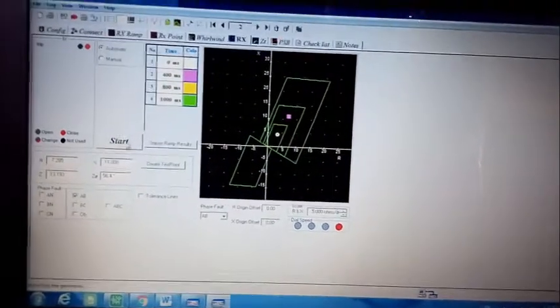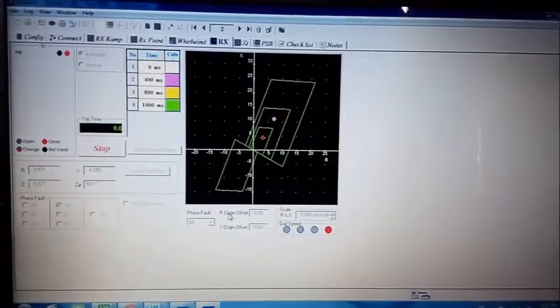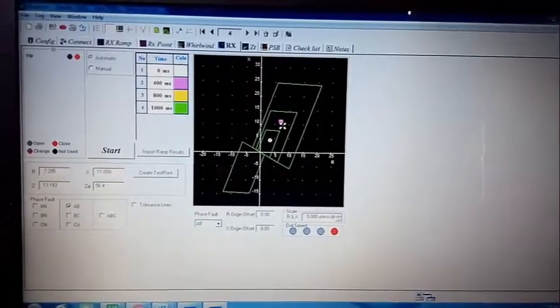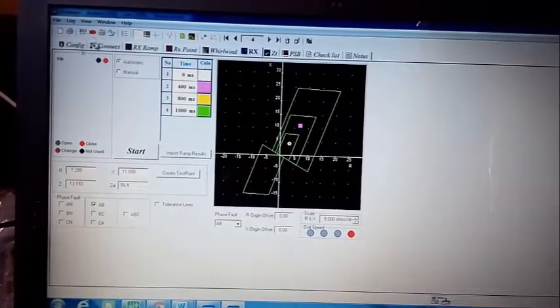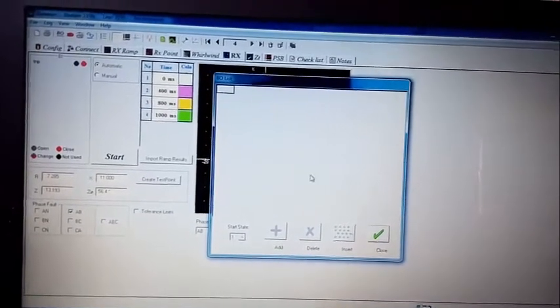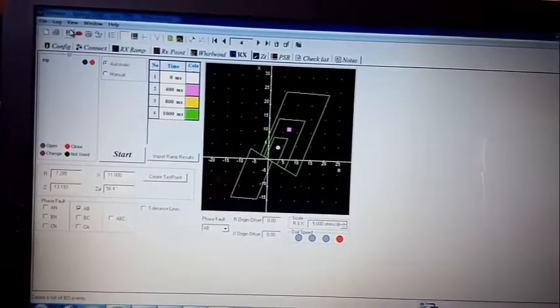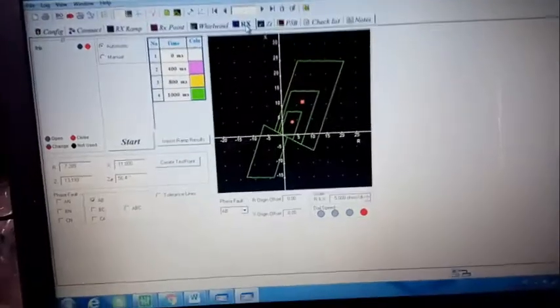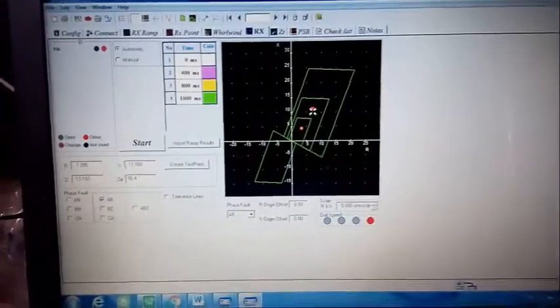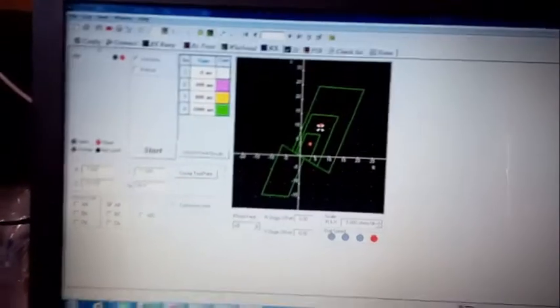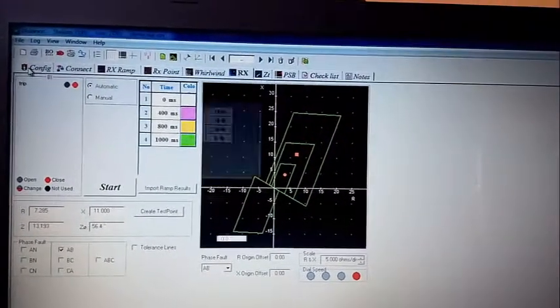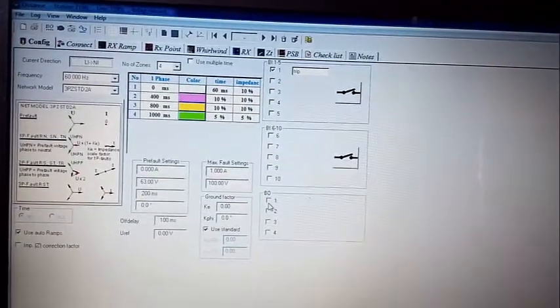Starting injection now. Zone number one shows '1' here and '2' here but not '1'. To understand why, we go to binary output. Previously it was showing zone two, but now we have enabled the Permissive Under Reach scheme, so we go to configuration to set up the binary output.